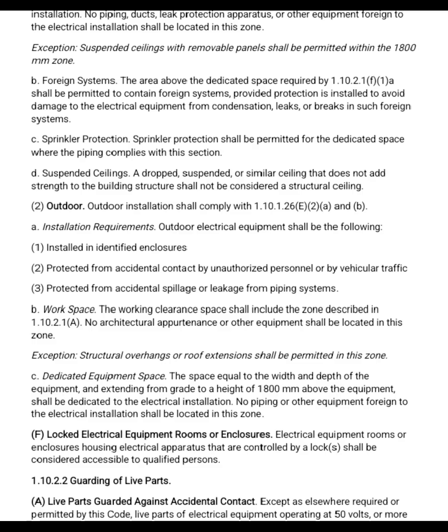C. Dedicated equipment space. The space equal to the width and depth of the equipment and extending from grade to a height of 1,800 mm above the equipment shall be dedicated to the electrical installation. No piping or other equipment foreign to the electrical installation shall be located in this zone. Locked electrical equipment rooms or enclosures. Electrical equipment, rooms or enclosures housing electrical apparatus that are controlled by a lock shall be considered accessible to qualified persons. Guarding of live parts. Live parts of electrical equipment operating at 50 volts or more shall be guarded against accidental contact, except as elsewhere required or permitted by this code.